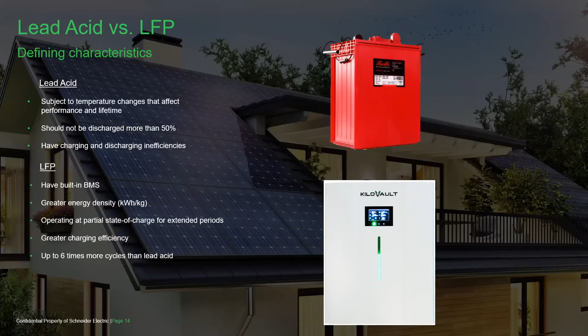They have greater energy density, so the kilowatt hours take up less room compared to lead acid. Partial state of charge tolerance is another great feature with lithium iron phosphate. They have better charging efficiency and offer up to 6 times more cycles than a lead acid battery. So when you talk about the cost differential, keep in mind that during the lifespan of a lithium iron phosphate battery, you could replace a lead acid battery bank up to 3 times.